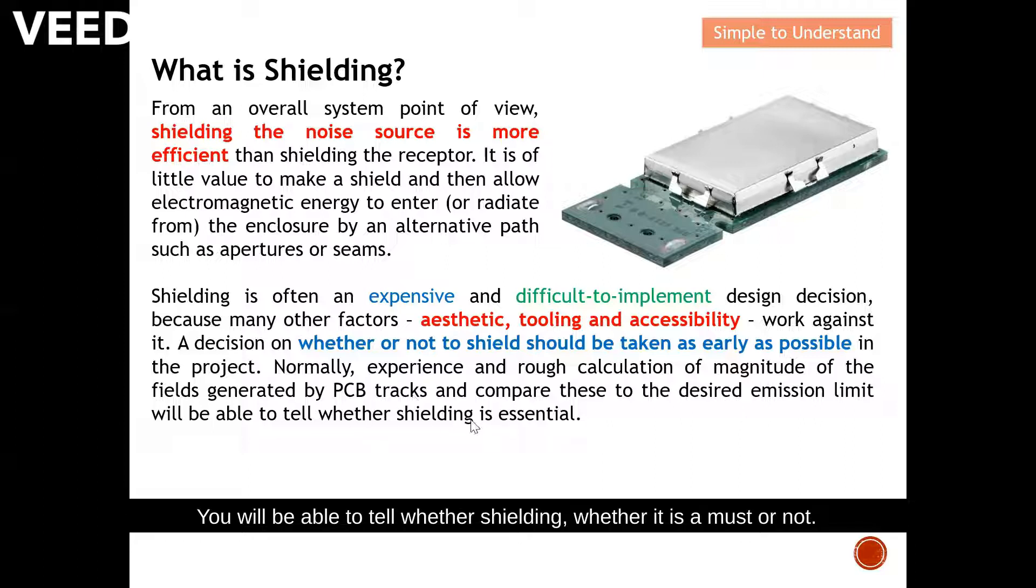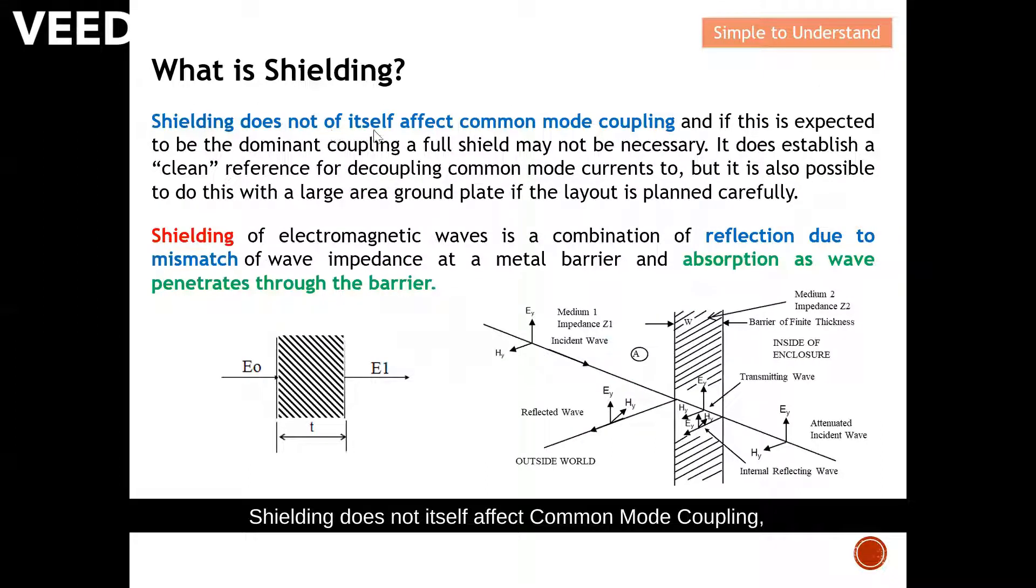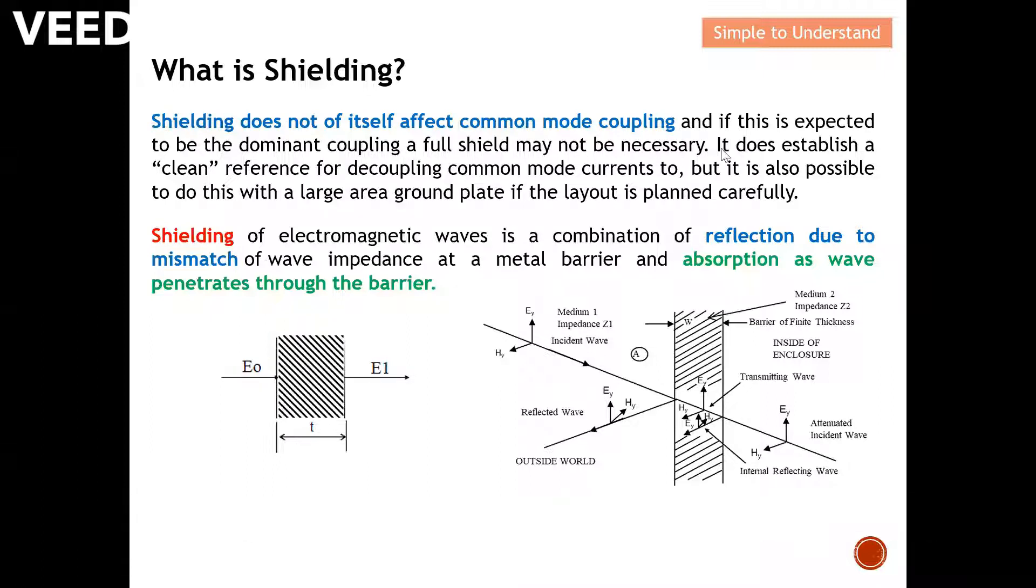Shielding does not itself affect common mode coupling, which means that shielding basically is not very effective against common mode coupling. If this is expected to be the dominant coupling, a full shield may not be necessary.